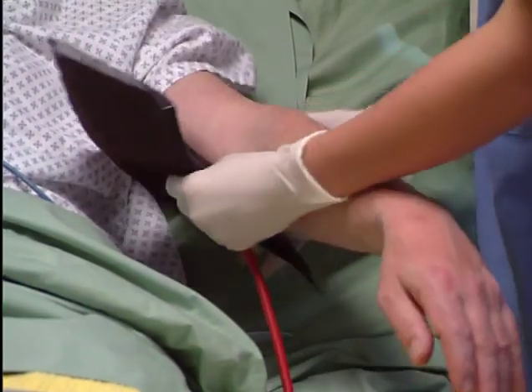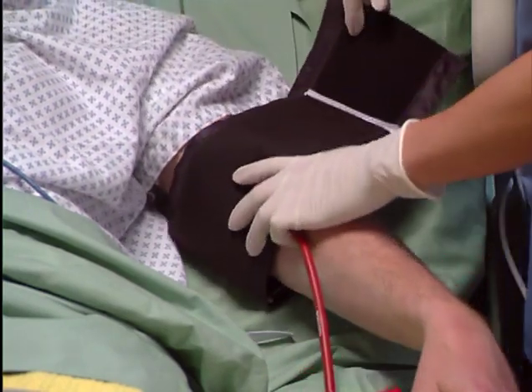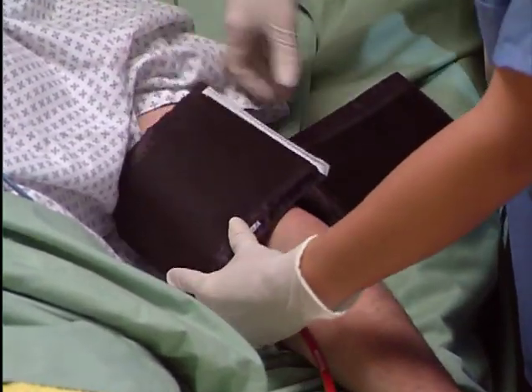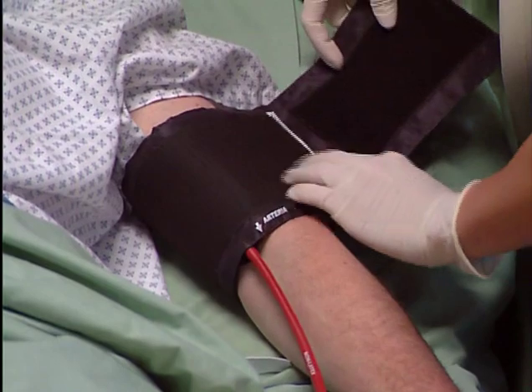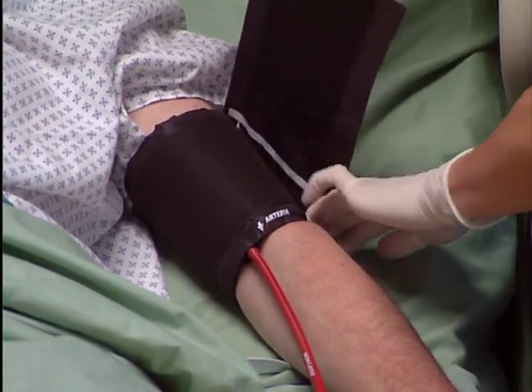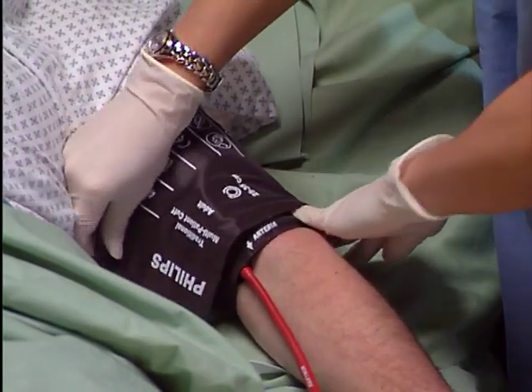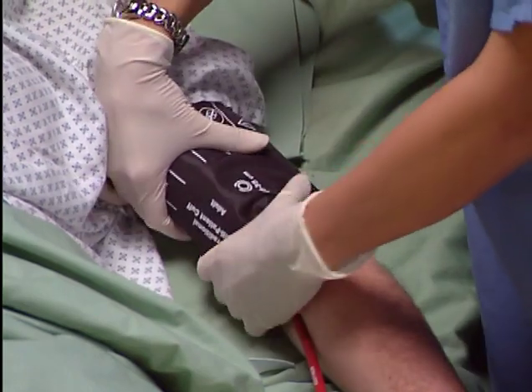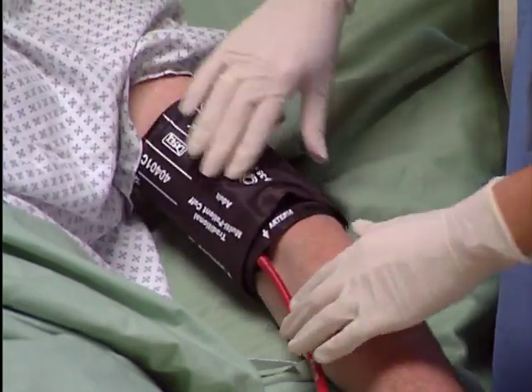The MRx can also monitor non-invasive blood pressure. The measurement can be done automatically or manually. The first step is to select the appropriate size cuff. A properly sized cuff should span approximately 2/3 of the distance between the elbow and the shoulder and wrap around the limb meeting in the indicated area.